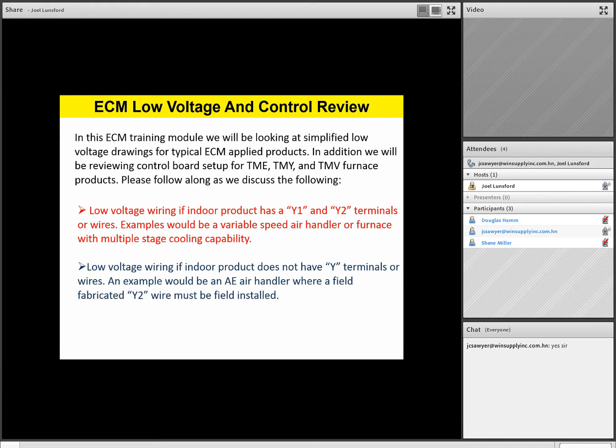In addition, we're also going to talk about how to wire a unit up if you don't have a Y terminal. So there are air handler products, specifically like the AE air handler. The AE air handler doesn't have Y terminals. It doesn't have a specific wire for Y1 or Y2. And so we're going to talk about how to wire that up, not only for single stage, but also it'll be utilized for a two-stage product. We'll show you how to wire that up for a two-stage product.